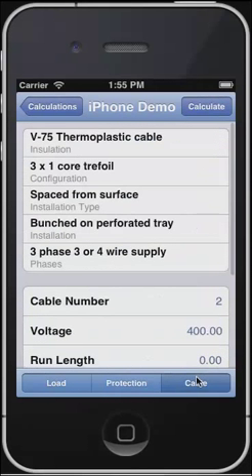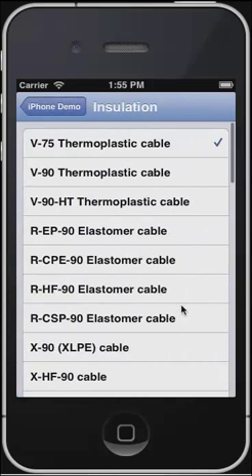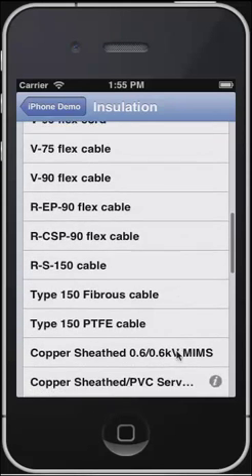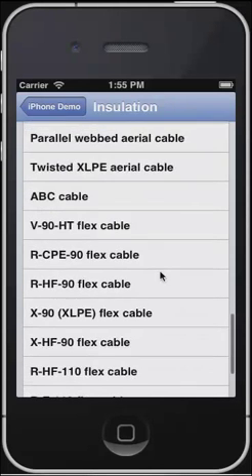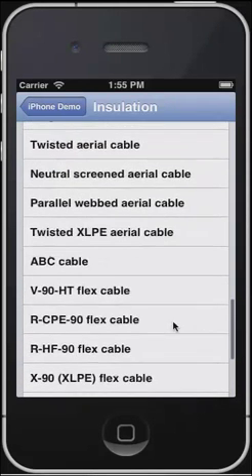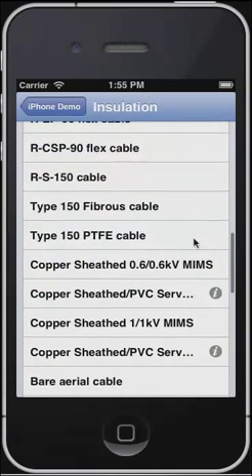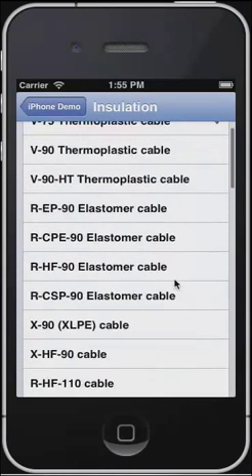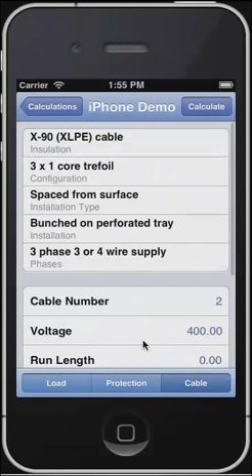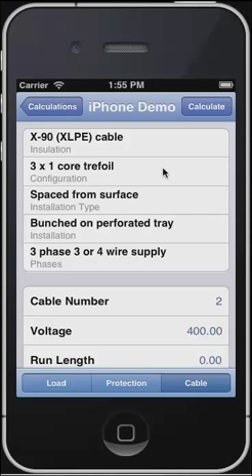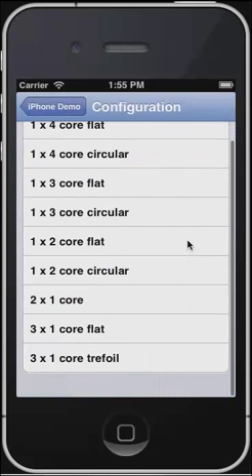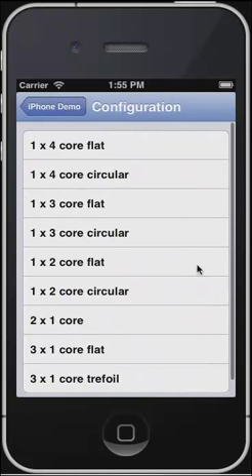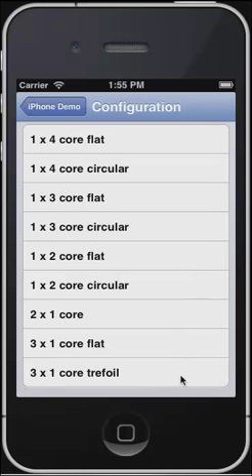Once we've finished, we go to the cable selection screen. Here we select the cable we're going to use. All cables inside AS3008 are available as selections at this screen. For this calculation we'll select XLPE. We can enter the configuration — whether it's 3x1, 1x3, flat, circular, or whatever. We will enter 3x1, called trefoil, for this calculation.